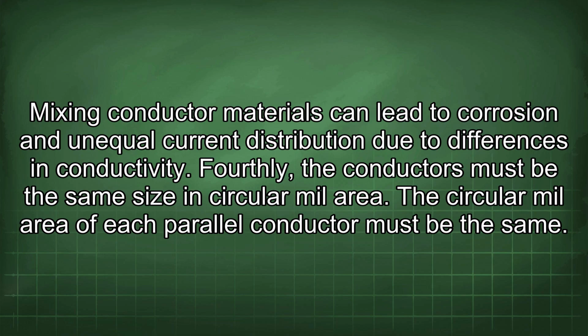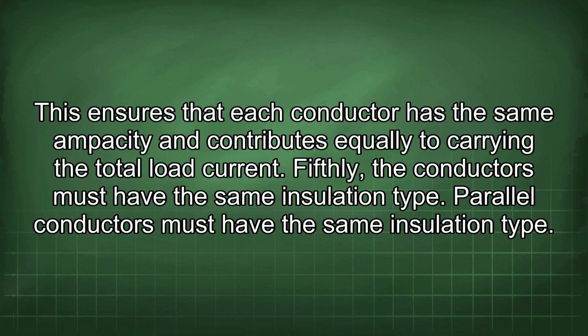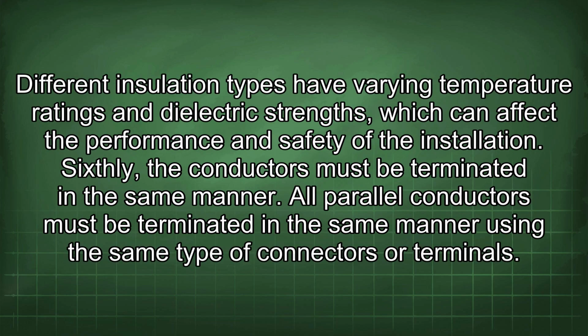Fourthly, the conductors must be the same size and circular mil area. The circular mil area of each parallel conductor must be the same. This ensures that each conductor has the same ampacity and contributes equally to carrying the total load current. Fifthly, the conductors must have the same insulation type. Parallel conductors must have the same insulation type. Different insulation types have varying temperature ratings and dielectric strengths, which can affect the performance and safety of the installation.